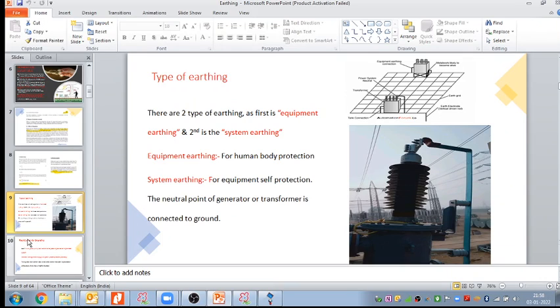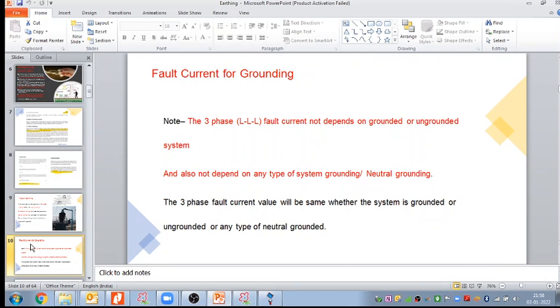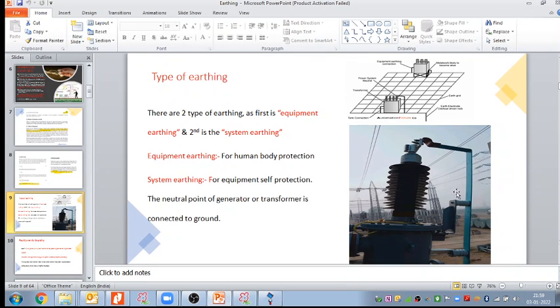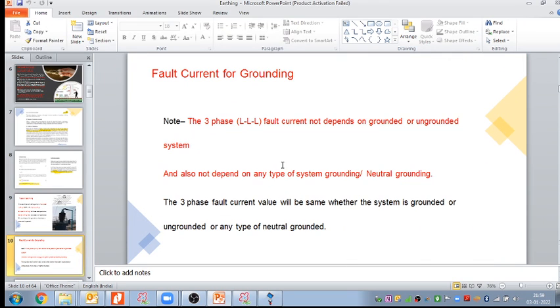Now the next: if we do the earthing, what type of fault current are we taking? The selection of the fault current for the grounding. The three-phase (LLL) fault current does not depend on a grounded or ungrounded system, and also does not depend on any type of system grounding or neutral grounding. The three-phase fault current value will be the same whether the system is grounded, ungrounded, or has any type of neutral grounding. For grounding we are not taking the three-phase fault current. We are taking the line-to-ground fault current, because that is what goes through the grounding, to the earthing strip, to the ground.